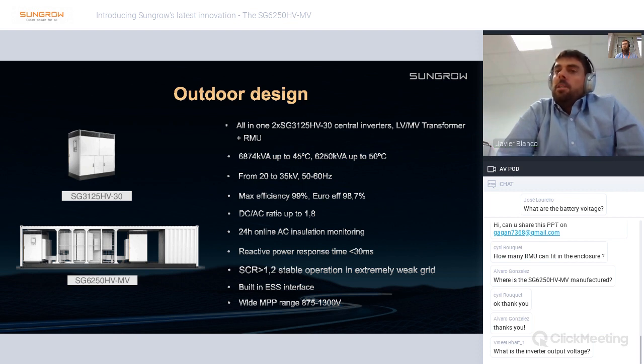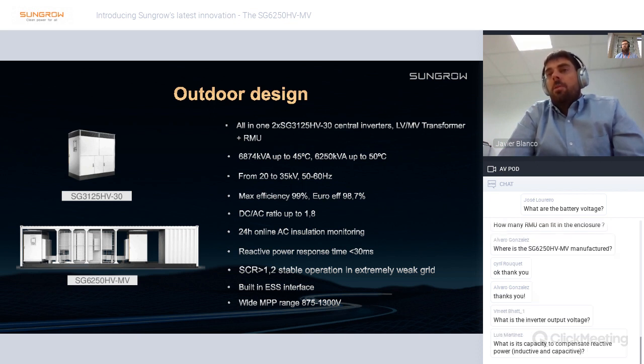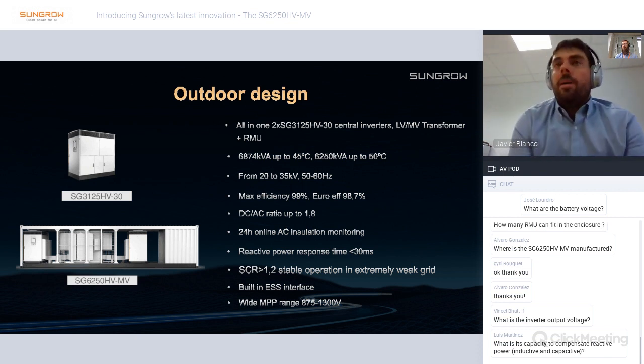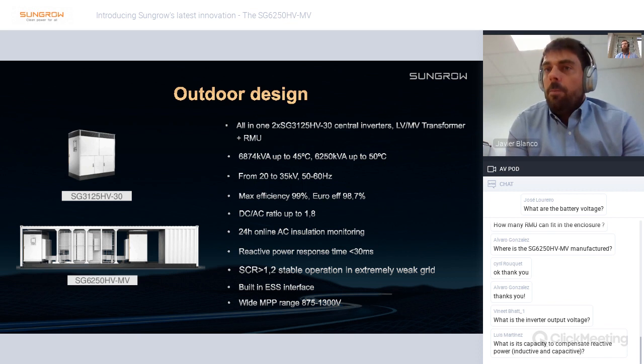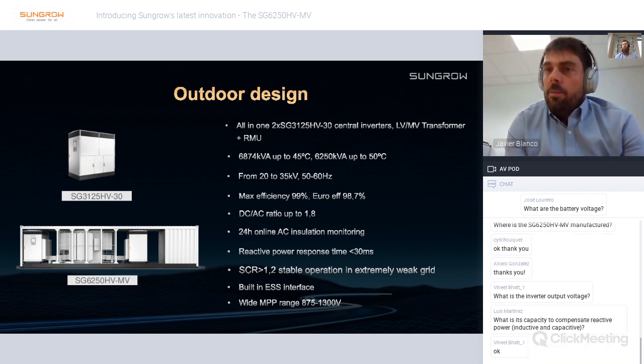Inverter output voltage is 600 volts. Like I explained, this means a wide MPP range in the inverter. We prefer to be a bit conservative here, because even though we could increase the power of the inverter by increasing the voltage, we prefer to be conservative, because we see that it is needed. When we go to demanding grid codes where we have to operate with a wide power factor range, and also with potentially high voltage at inverter terminals, I think it's worth having a wide MPP range to support all these eventualities. Otherwise, if the MPP range is too narrow, when we have to support reactive power, you can lose yield because of that.